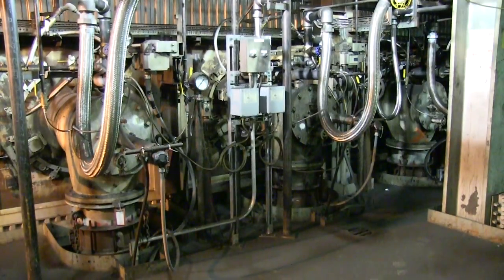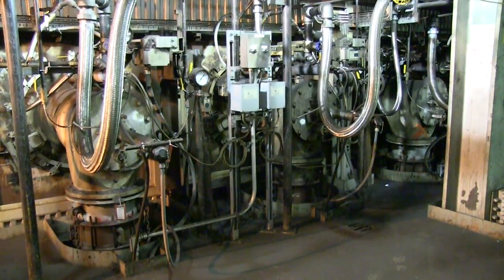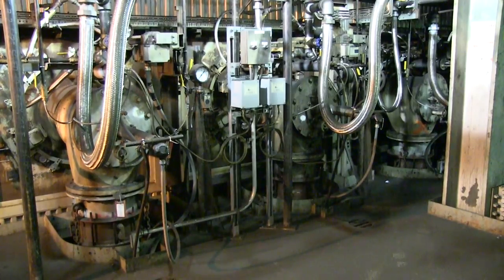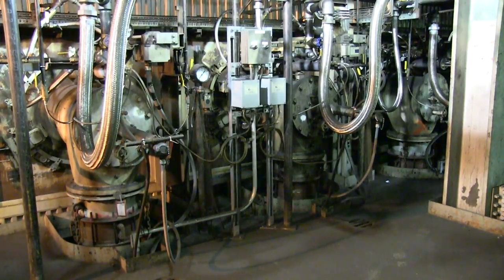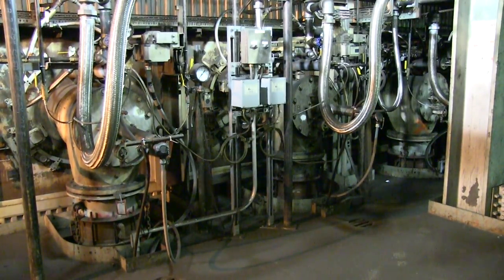The pulverized coal and air are blown into the boiler from burner ports on the boiler walls and ignites. Each of these ports is about 3 feet across. A massive fire with temperatures that can reach 2,500 degrees Fahrenheit burns inside the boiler and heats ultra-pure water inside 1-inch tubes to more than 1,000 degrees, causing the water to flash instantly into steam.